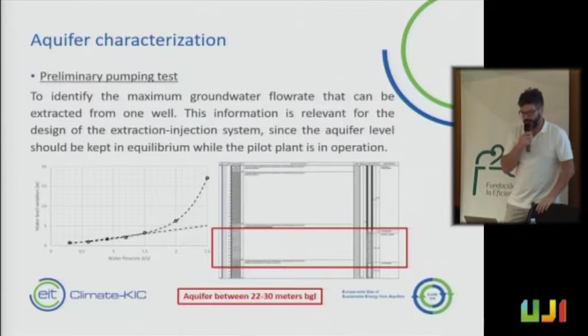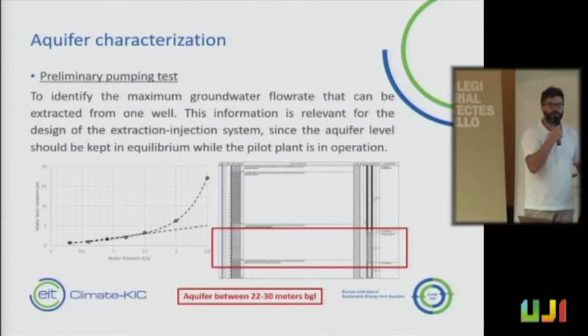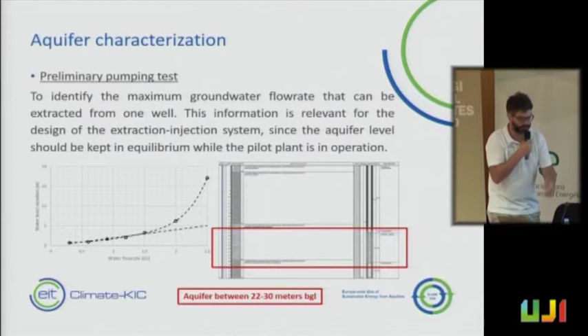And that was really important information to size and design the extraction system. So we have 3 wells to reach the groundwater flow rate needed to feed the heat pumps and the chillers. If we need more water, we have to realize more extraction wells and more injection wells. That means higher cost, as you will see.